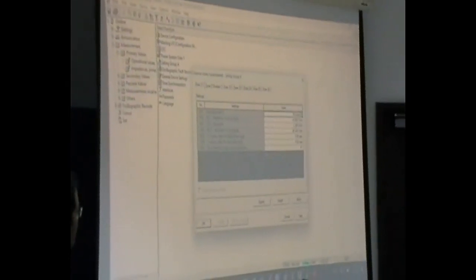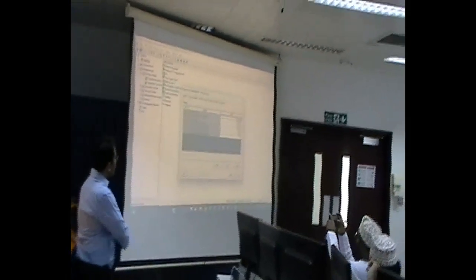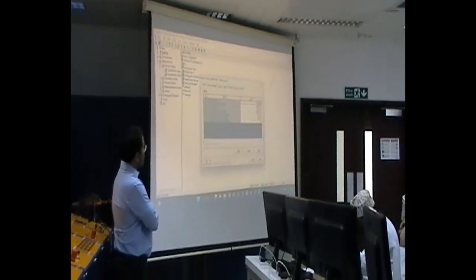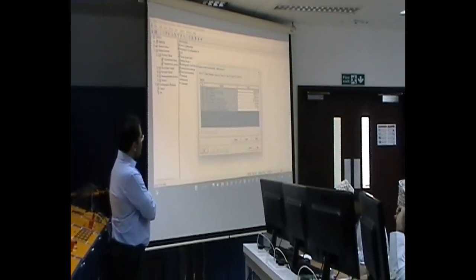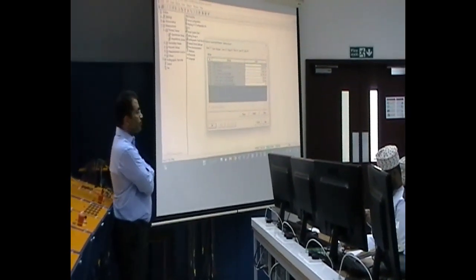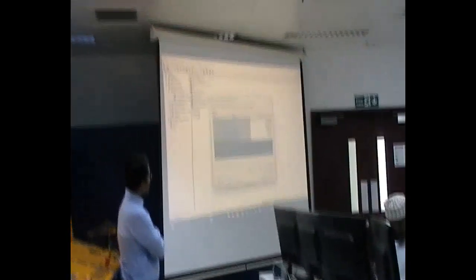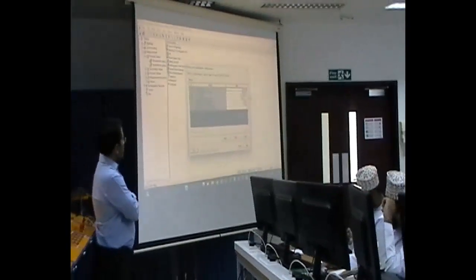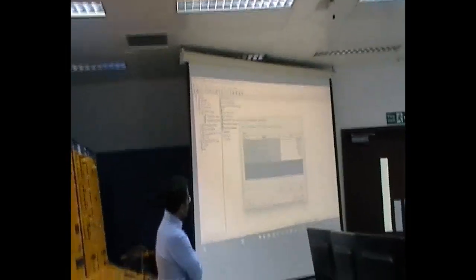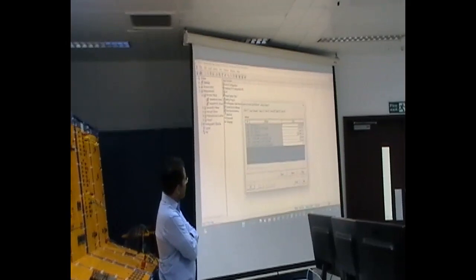And we have 3 types or 4 types of setting. We have basically the relay work in ohms. So we have for the impedance either reactance or resistance. So we'll have the same reactance setting for phase and earth, but the resistance setting will be different from phase to earth. So here, first one is resistance phase to phase, which is 19.8. For which zone? Zone 1. We're in zone 1. The reactance setting is 2.38. 2.38.